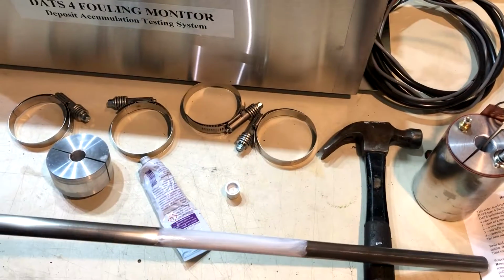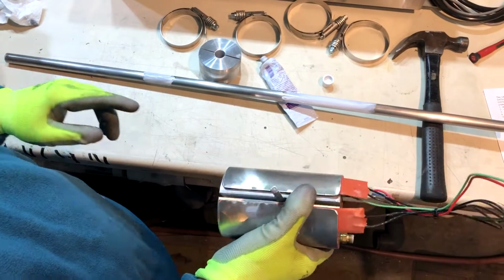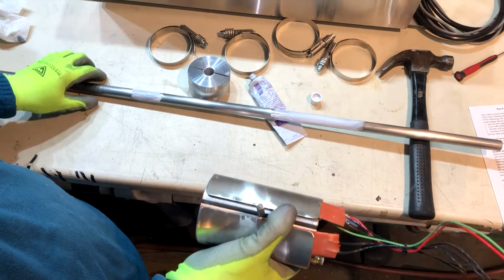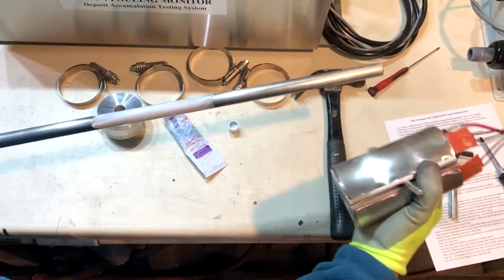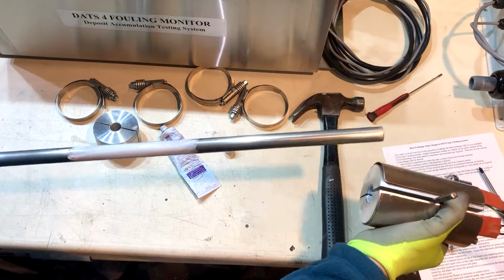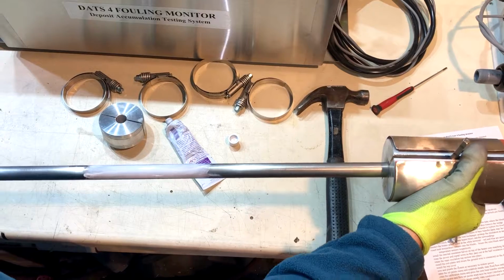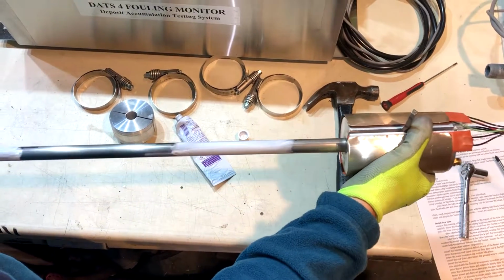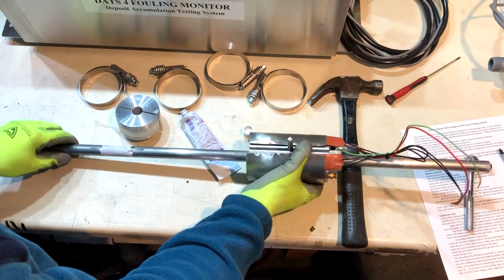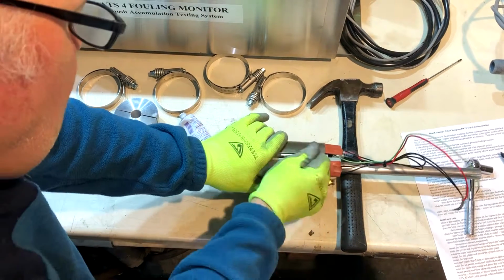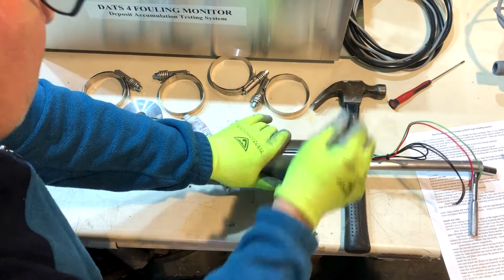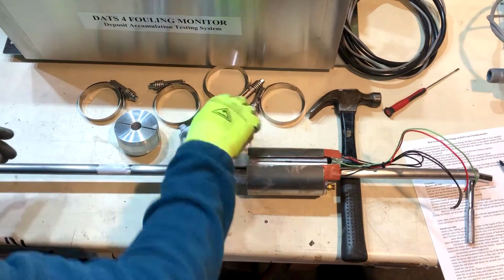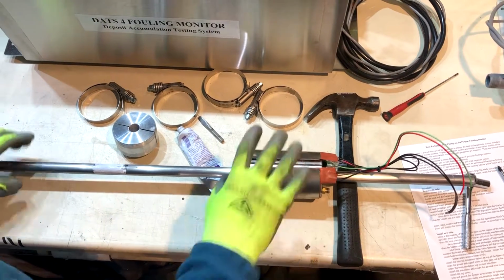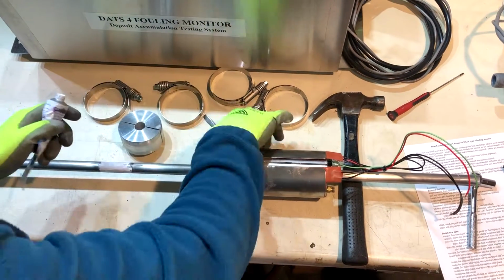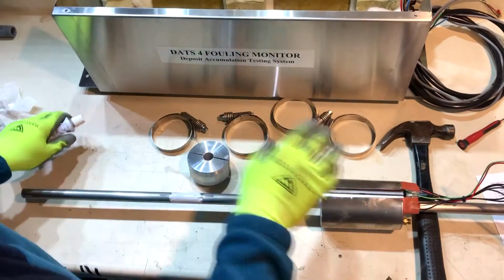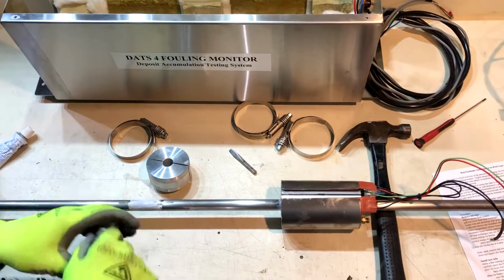Almost translucent layer. Okay, so the heater block has been cleaned on the inside and inspected to ensure that it's blemish free, and the inside or the edge of the tube is not sharp, and now we gradually and carefully introduce this tube and block together, slide it over to the appropriate position, and wiggle our wedge out of place. The block clamps closed slightly, but not entirely. So it's important not to move the tube about as you're doing this. Now we'll put the clamps on the OD of the block and holding it in place.